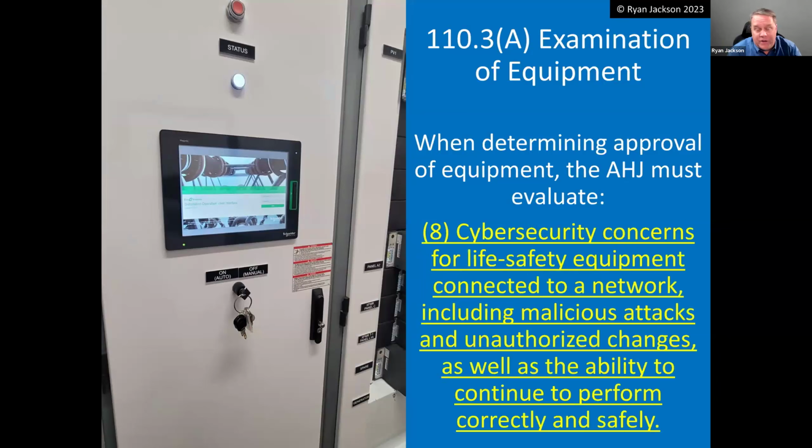You know, this piece of equipment here is not your grandma's switchboard. A modern switchboard today, you can buy them with a full-blown Windows operating system. And I guess we have kind of a gorilla in the room. I mean, the elephant in the room, rather. Two days ago, whenever it was, we had that massive outage, right? Imagine if this was a hospital. And we've got this system here where you can log into it with your username and password and change the characteristics of the circuit breakers. Now, that's fine. There's nothing wrong with that. We can walk up to a lot of breakers and do that with screwdrivers, right? They're designed to be adjustable.